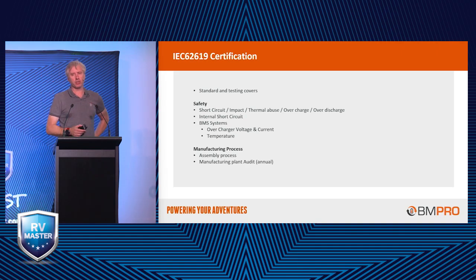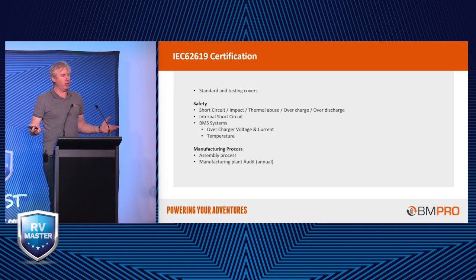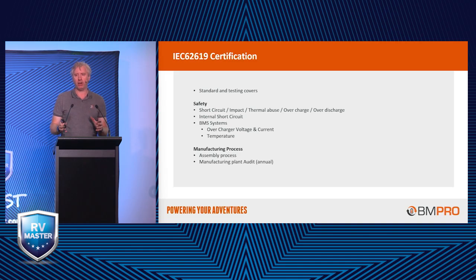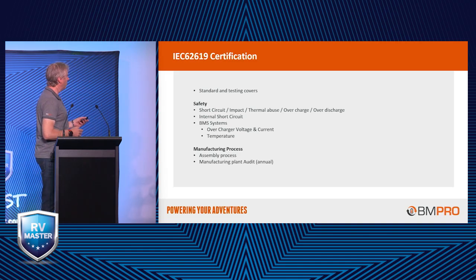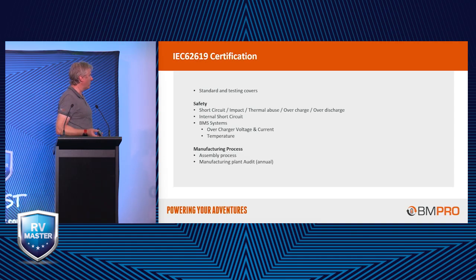What does that mean for you as a consumer? It means you can have comfort that the battery has been tested as a complete unit. If it's not tested as a complete unit and just tested as an individual cell, you risk the fact that it's not going to work properly. The BMS is the most important part of it, so it needs to be tested with the BMS installed in it. What does the BMS do? It'll help you out with things such as short circuit, impact, thermal abuse, overcharge, over-discharge, and short circuits on battery cells, all those types of things.